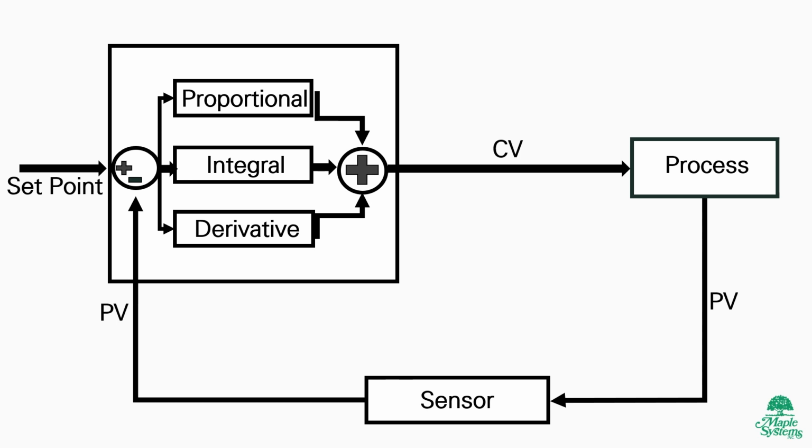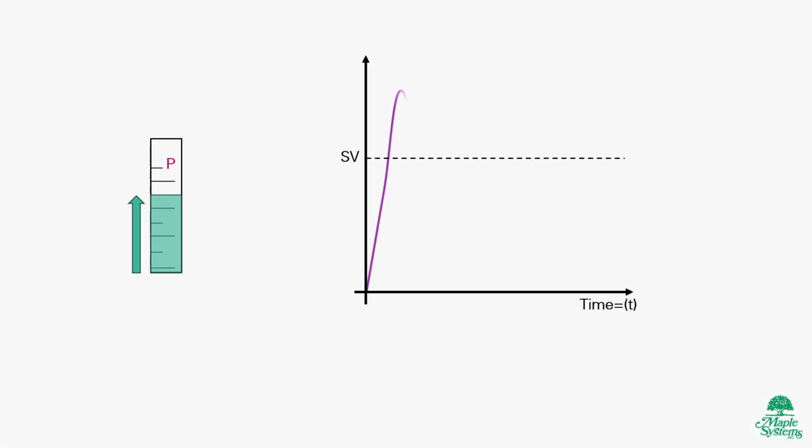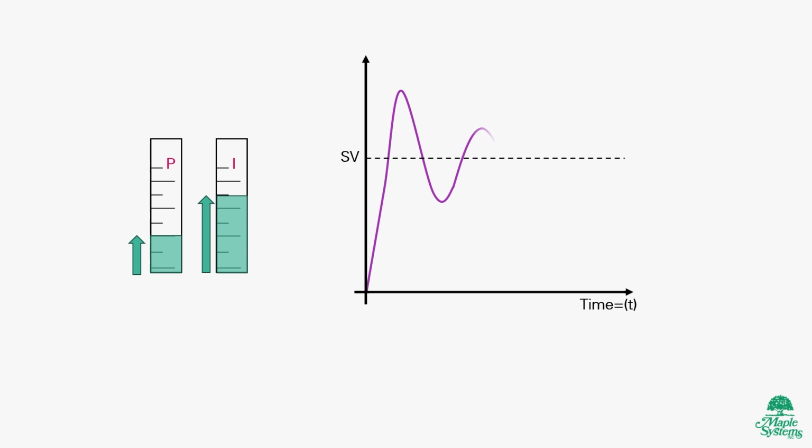A measured approach is starting with the low gain with integral and derivative disabled. As you incrementally adjust the gain by doubling the value, the process begins to oscillate, so adjust the gain value down by 50%. Now apply a small integral value and monitor the process. Double the value incrementally until oscillations occur. Then cut the integral by 50%. After this, you should be close to the set value and begin the fine-tuning process.